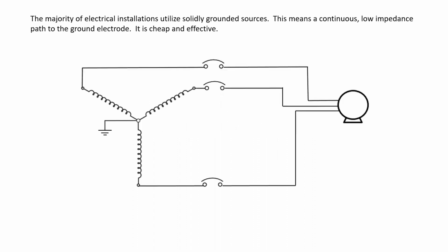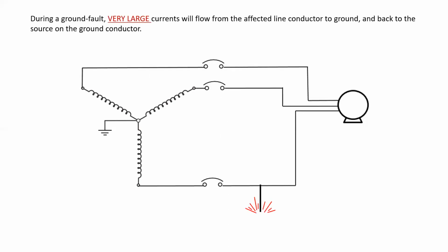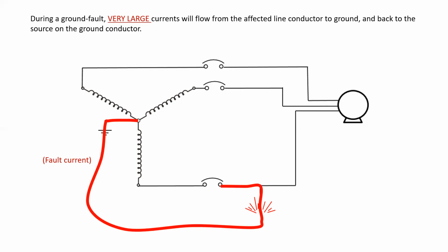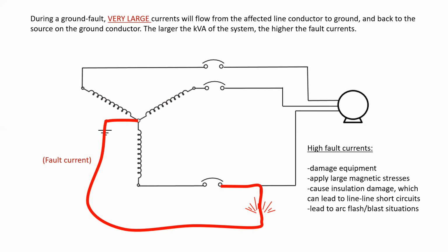The majority of electrical installations utilize solidly grounded sources. This means a continuous low impedance path to the ground electrode. It is cheap and effective. During a ground fault, very large currents will flow from the affected line conductor to ground and back to the source on the ground conductor. The larger the kVA of the system, the higher the fault currents.